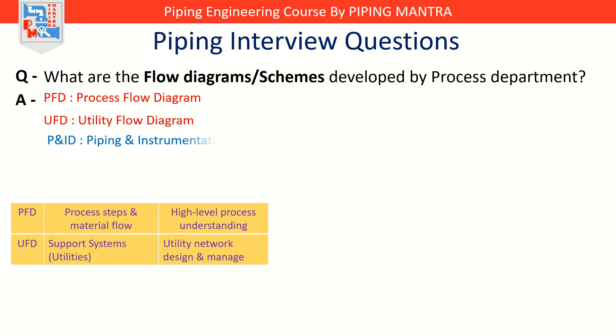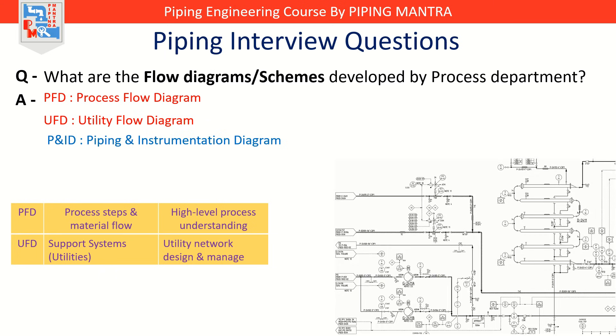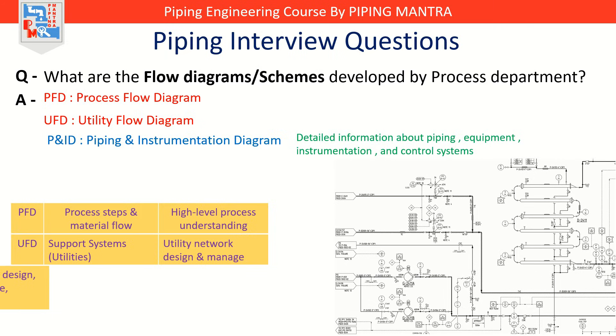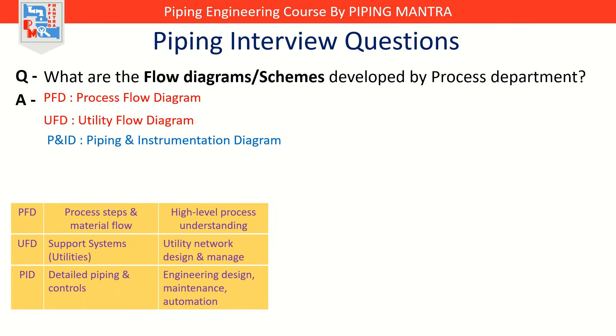Third is P&ID, that is Piping and Instrumentation Diagram. If the PFD is a map, the P&ID is like the blueprint of a car design — highly detailed and precise. It shows every piping detail, equipment, instrumentation, and control systems. Here you'll see valves, pumps, instruments like pressure gauges and flow meters, and control loops and exactly how they're connected. This is the diagram used by engineers, fabricators, and maintenance teams to actually build and operate the plant.